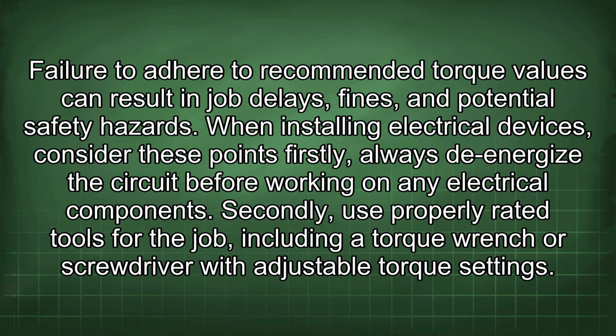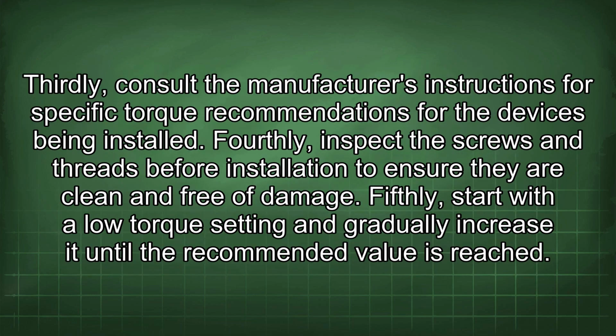Firstly, always de-energize the circuit before working on any electrical component. Secondly, use properly rated tools for the job, including a torque wrench or screwdriver with adjustable torque settings. Thirdly, consult the manufacturer's instructions for specific torque recommendations for the devices being installed. Fourthly, inspect the screws and threads before installation to ensure they are clean and free of damage.